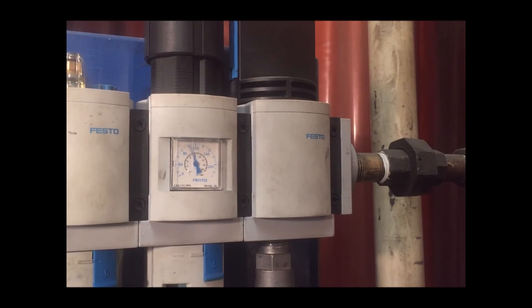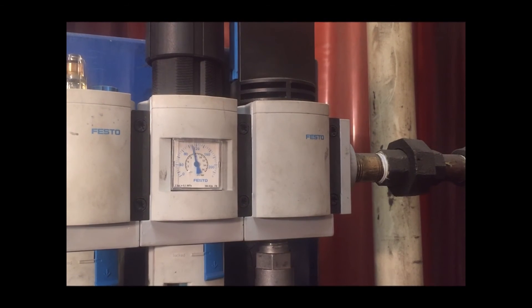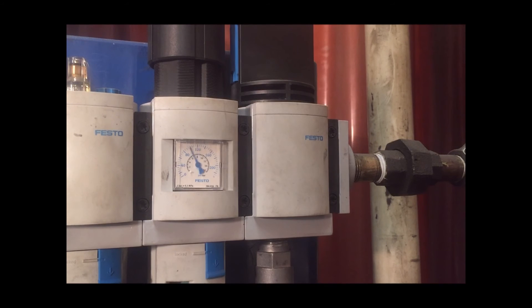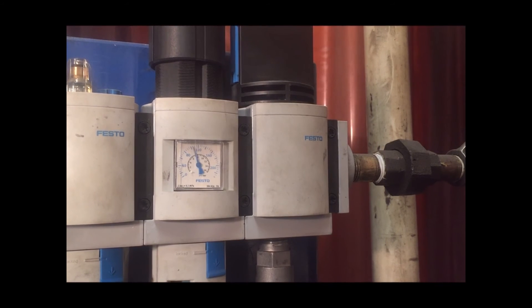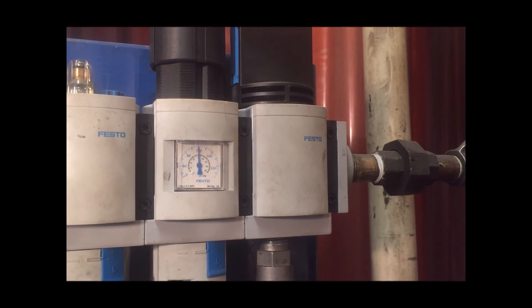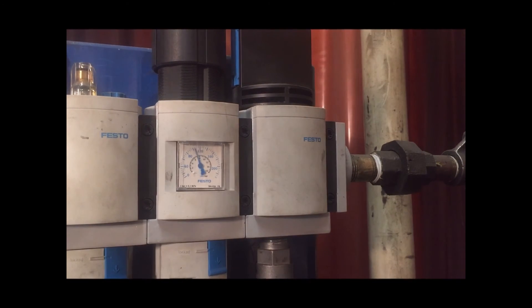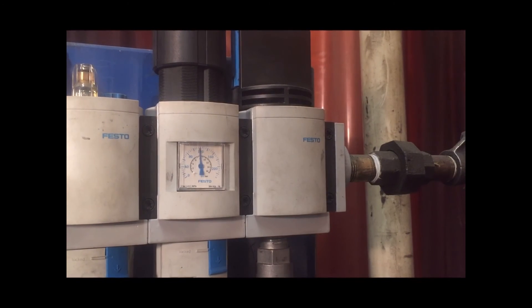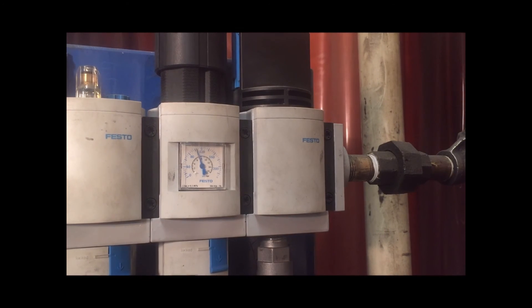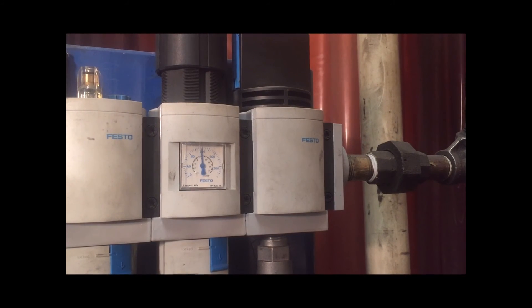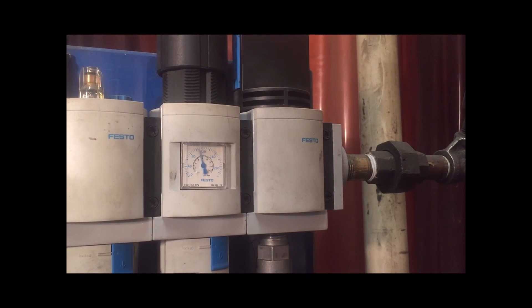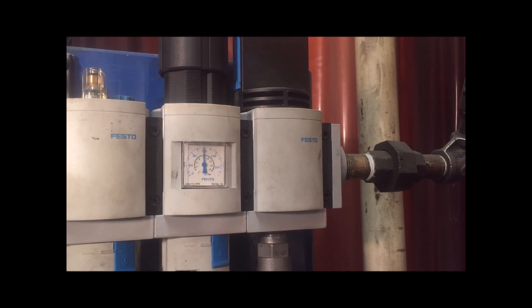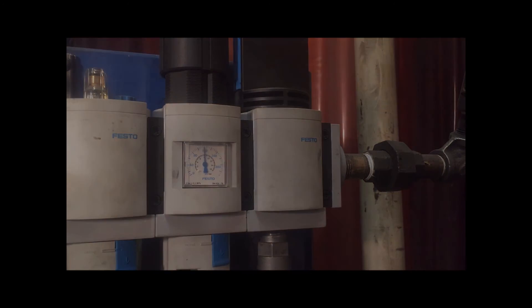In other words, if all your tools need 90 psi, then having your line pressure at 175 psi and regulating it down doesn't help you as much with volume as having a bigger tank at 120 psi might, while letting your compressor work less.